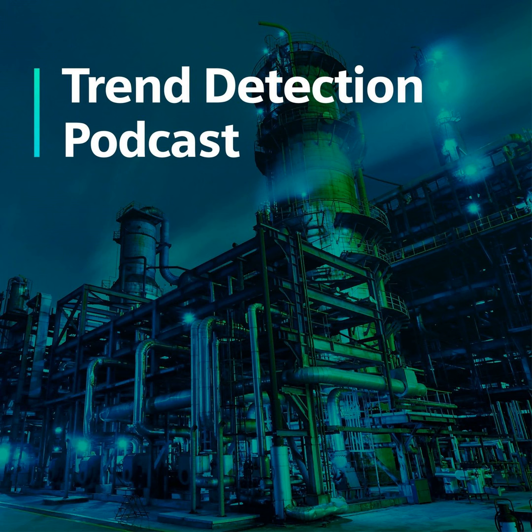It's also really key to add that in condition monitoring, but particularly in predictive maintenance, more due to the way you set it up, operational state for your assets is really important. So if you're monitoring the condition of an asset, but the operation changes all the time, you've got two options. Either you make sure that you're only capturing data at the same point in the cycle, or when it's producing the same thing, etc. Or you also ingest information about the state of the operation. So for example, if you've got a fan connected to a variable speed drive, or like your desk fan where it has a number of buttons on it to change the speed of it. If you press the higher button or you increase the speed on your fan, it's going to be blowing more air, so it's going to draw more current.